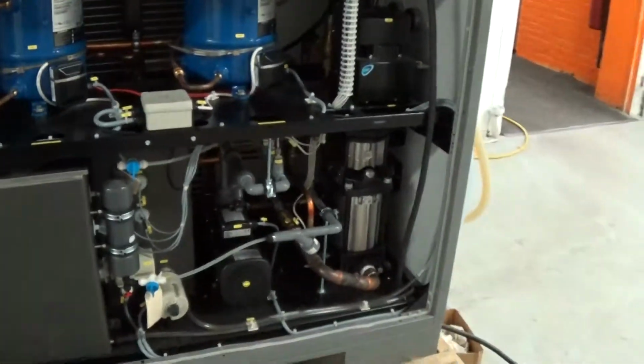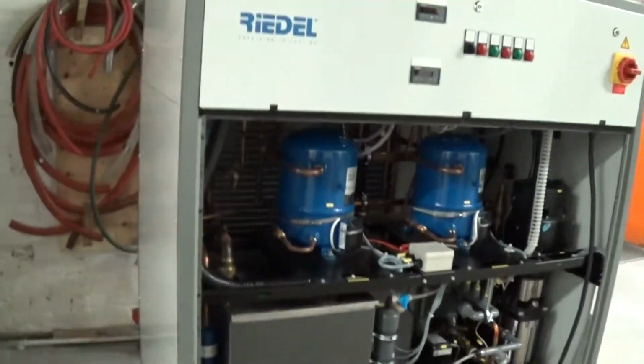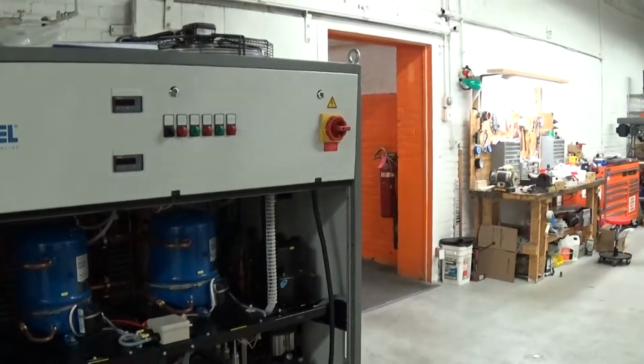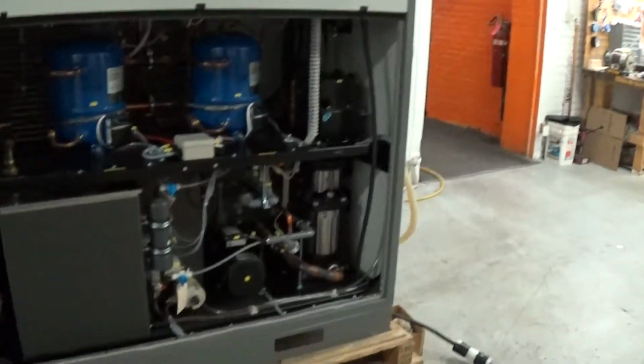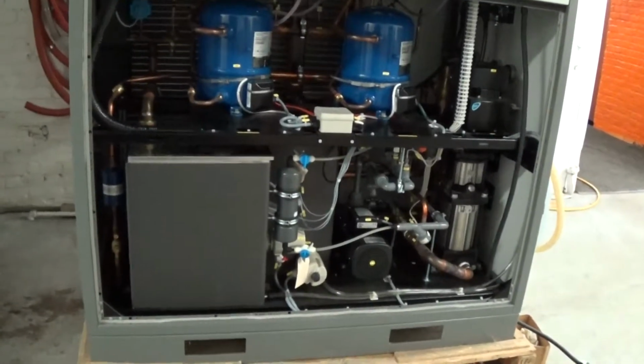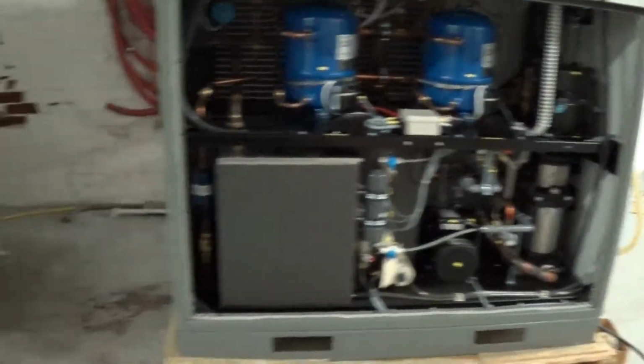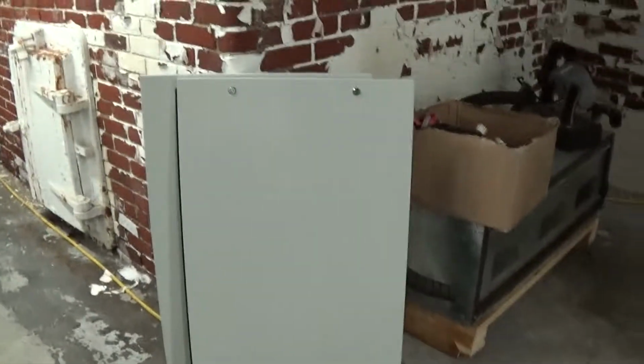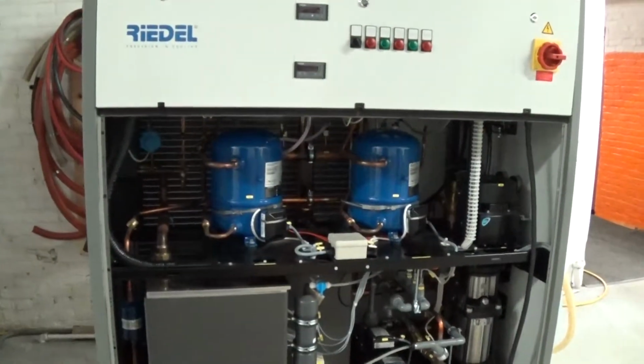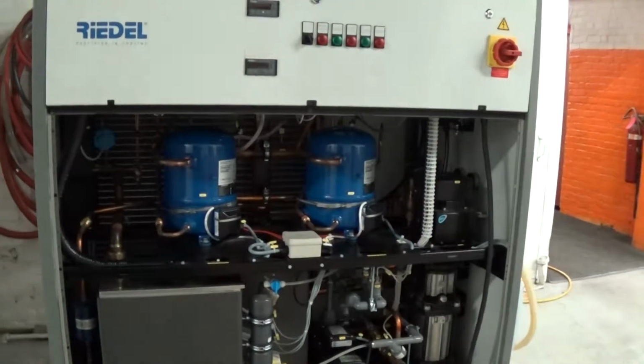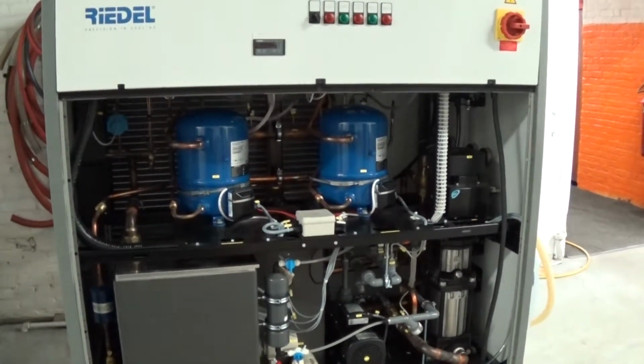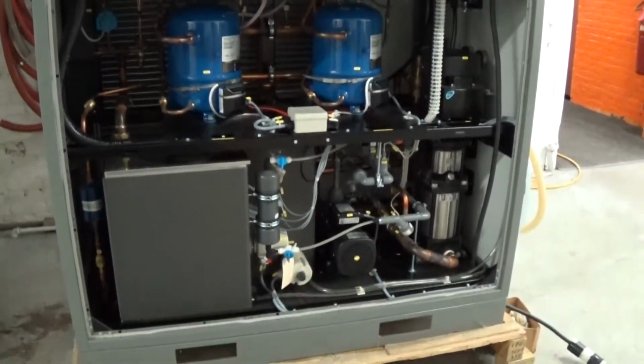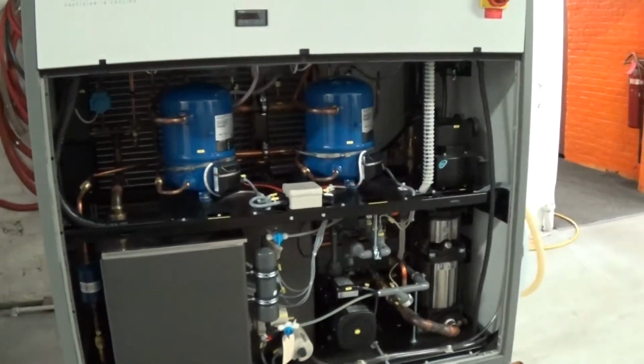This chiller here, again, the Riedels are amongst the most nicely engineered units we've seen. This unit here has to have the side covers on, which we have here, to provide proper airflow through the condenser coil. So video number 2 I'll start in a second after I get the side covers on, and we'll power the unit up.